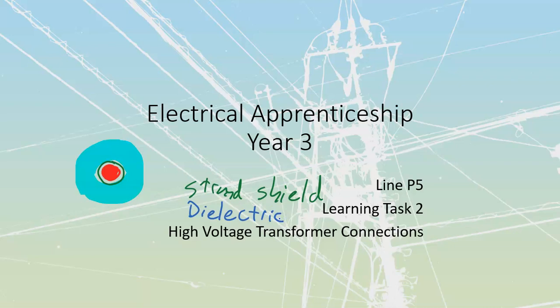Going back to second year, recall what you learned about capacitors: a capacitor is two charged objects of differing polarity with insulation in between. That insulation has its orbitals distorted. If you distort an orbital far enough, you break the electron bond, and at that point you get current flow. Anything to do with this insulation, we refer to as the dielectric on our high voltage cable.